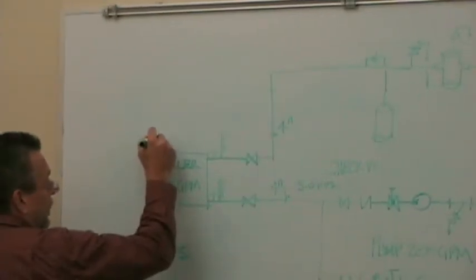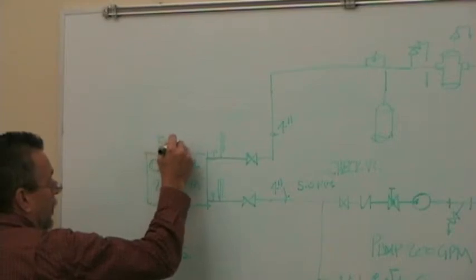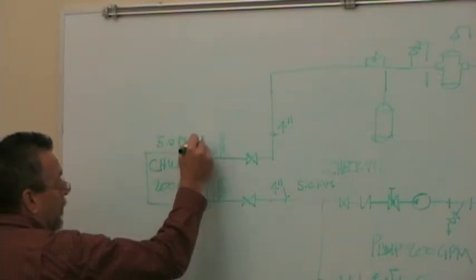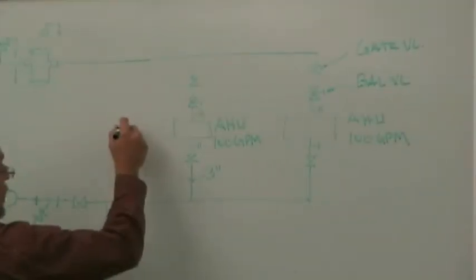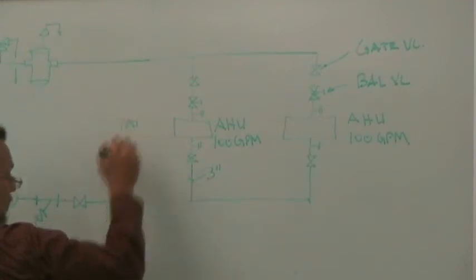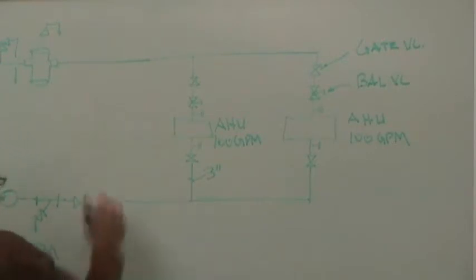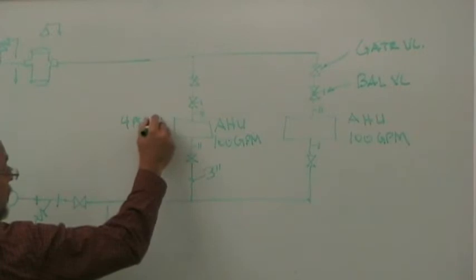And a chiller, I get a selection on a chiller, and this particular chiller at 200 gallons a minute has, say, a 5 PSI pressure drop. My coils from my air handling unit are going to be given to me, and they're probably 7 PSI. I'll make that a little less. Say 4 PSI pressure drop in each one. Okay. So I know my chiller, I know my air handling units, and I've got this piping system that's running out through the building.